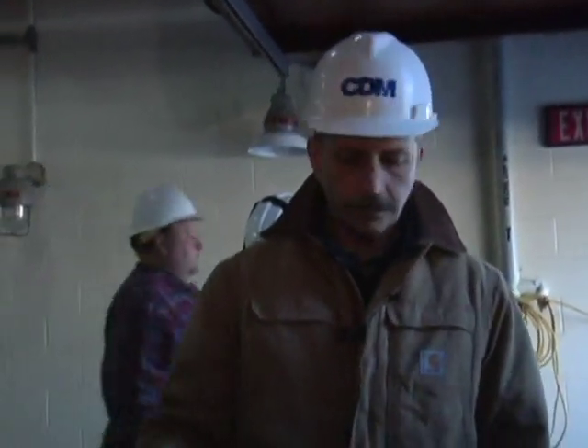Okay, as the wastewater comes into the building, there are a couple of bar screens here. The flow enters through either one of the channels. There is a flow measuring device that's looking at the water level on the upstream side of the bar screens. There's one upstream as well as downstream. The flow measuring device is located here in the center of the channel. That's looking at the water level, so that when your system is running in automatic, if it sees a high differential level, namely the bar screen has become plugged with material and the water has started to back up in the channel and back up into the interceptor system, that high level will trigger the screen to come online. Other than that, the screen would normally be set for timed operation.